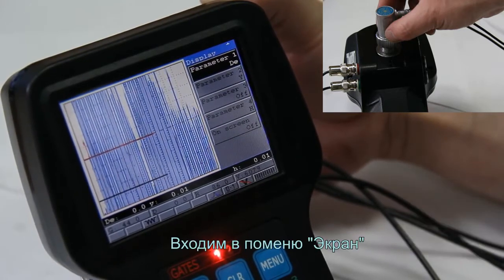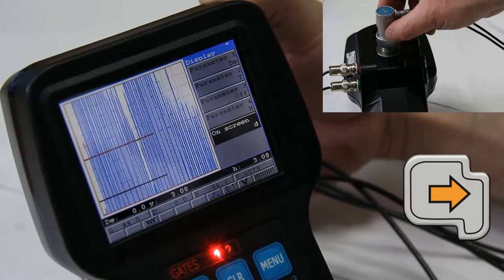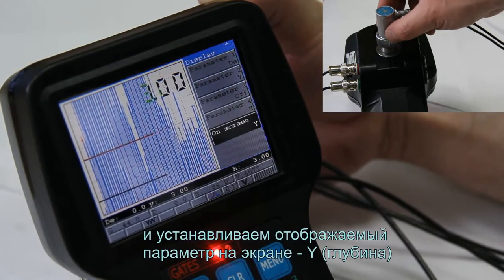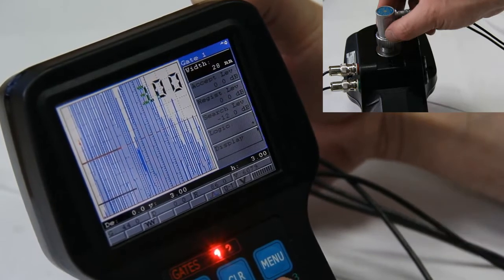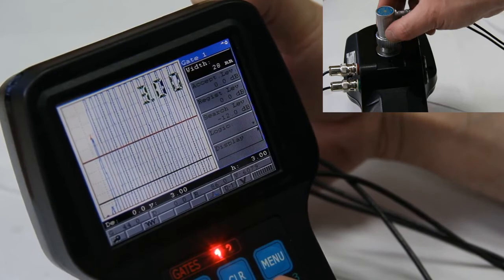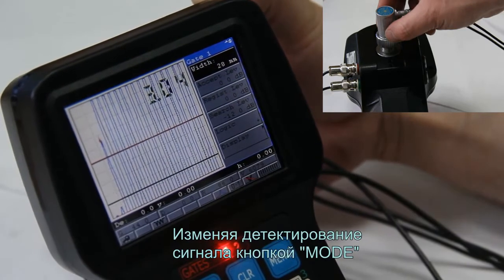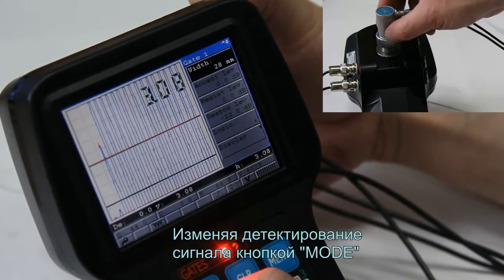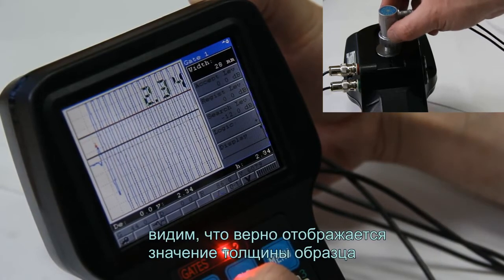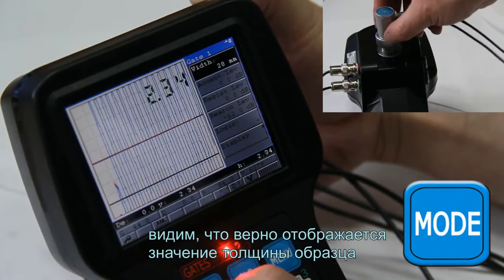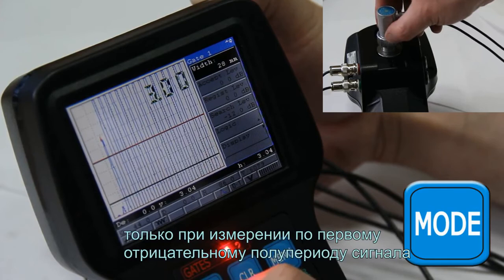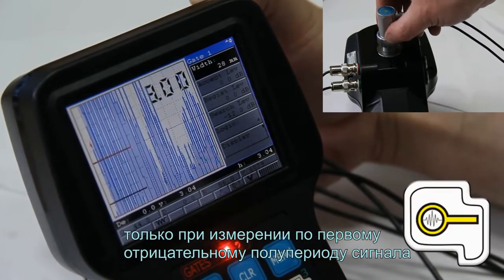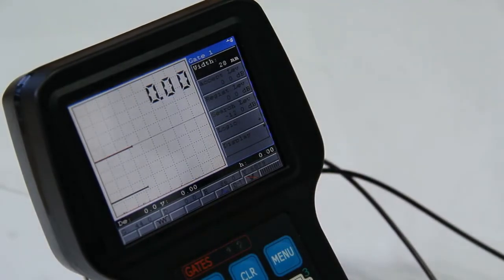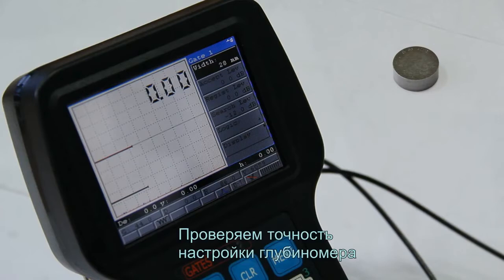Enter the Display submenu and set up the parameter displayed on the screen, Y coordinate depth. When changing the signal rectification using the mode key, observe that the block thickness value is displayed correctly only when the measurement is performed by the first negative half period of the signal. Remove the probe from the built-in block. Check the accuracy of the depth gauge setup.